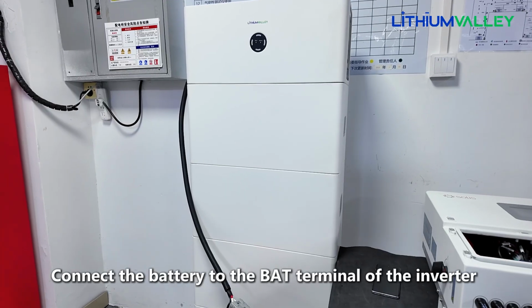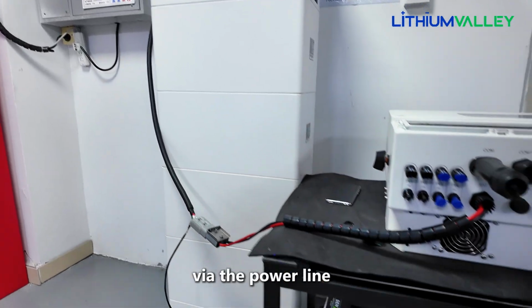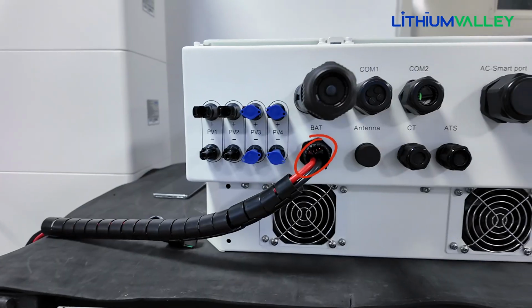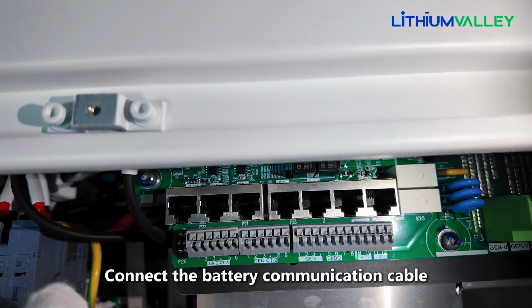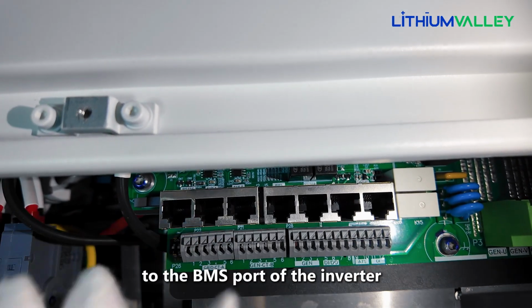Connect the battery to the BAT terminal of the inverter through a power line. Connect the battery communication cable to the BMS port of the inverter.